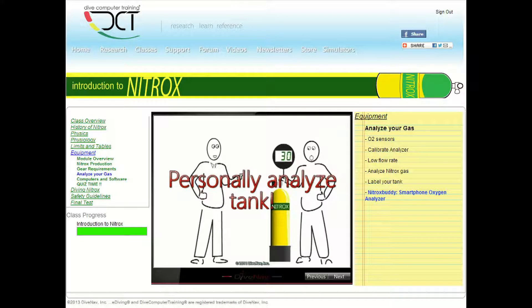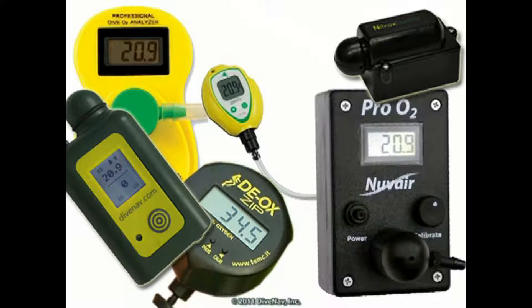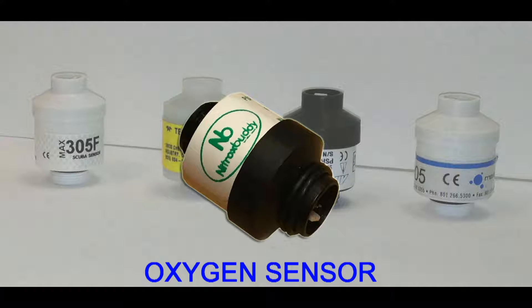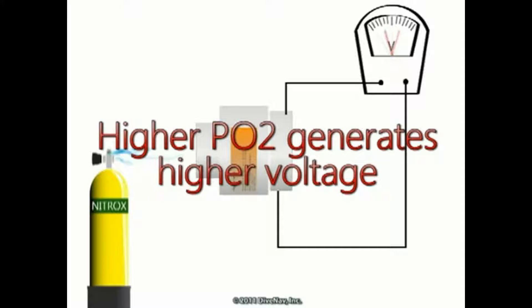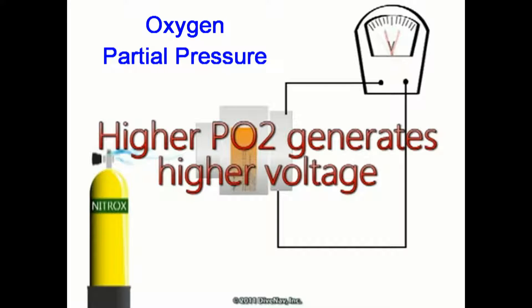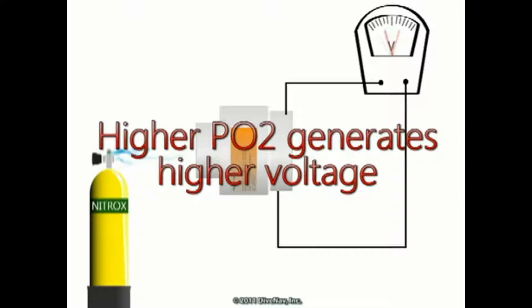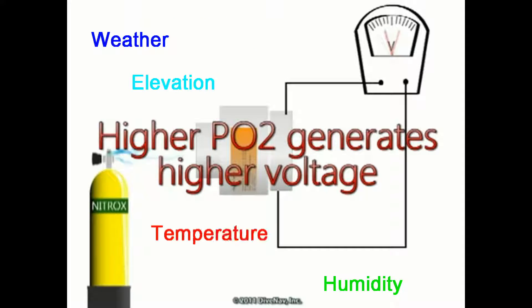As explained in our introduction to Nitrox online class, at the heart of every oxygen analyzer there is an oxygen sensor. The oxygen sensor is a chemical device that measures the partial pressure of oxygen, and as such, it is affected by changes in atmospheric pressure.